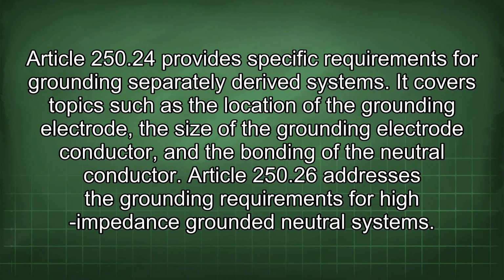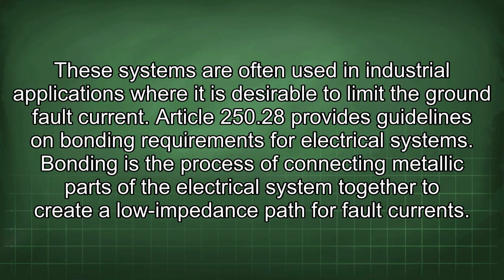Article 250.26 addresses the grounding requirements for high-impedance grounded neutral systems. These systems are often used in industrial applications where it is desirable to limit the ground fault current.